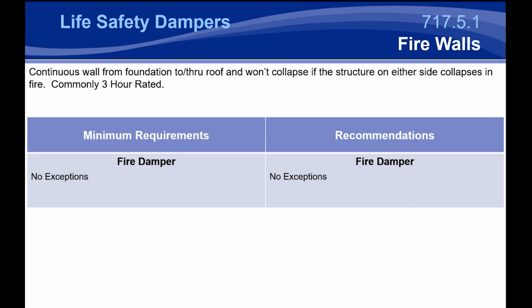Most of the applications I've seen where this comes into play happen when there's, say, a building owner that takes over multiple occupancies that are sharing a firewall, but doesn't necessarily change the address for those occupancies. So those occupancies may have multiple addresses and a firewall bisecting them, but the building owner may want to upgrade the HVAC system to be able to utilize airflow across that fire barrier. I have seen cases where, instead of putting in a fire damper in that application, the owner changes the certification or changes the address with the jurisdiction and it becomes all one occupancy. It's very rare to see firewall penetrations, but if you do, you do have to protect these with a fire damper.